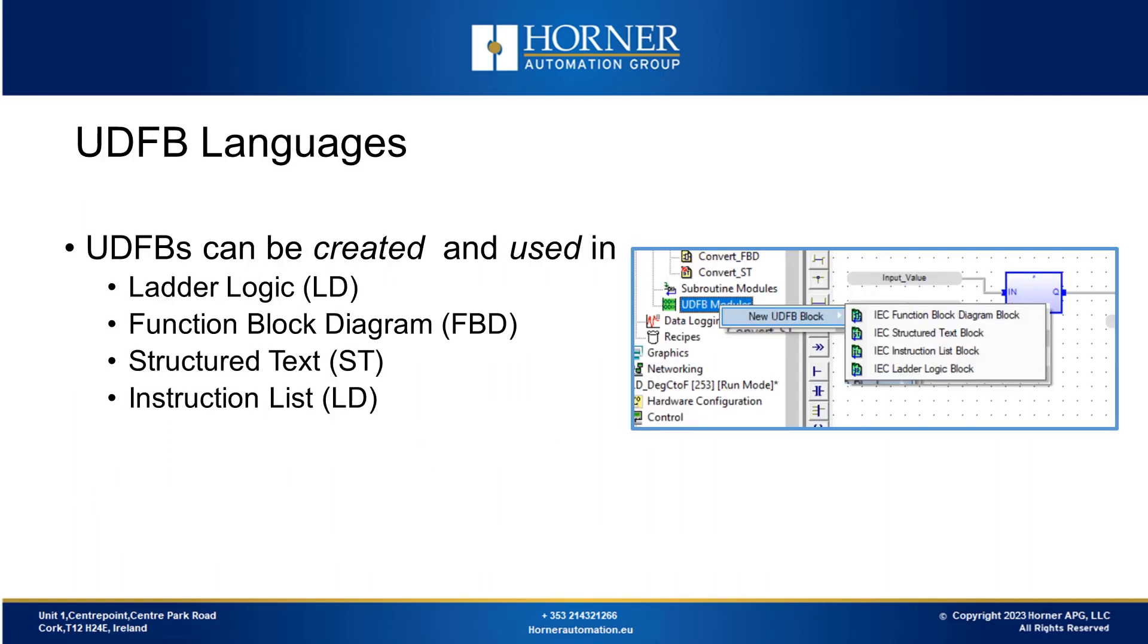The languages available for creating and using user-defined function blocks are consistent across the board. They encompass three widely used options: ladder logic, function block diagram and structured text. Additionally, instruction list can also be utilized, although it's not as commonly used these days. However, sequential function chart is absent from this list, as it's not suitable for working with user-defined function blocks.